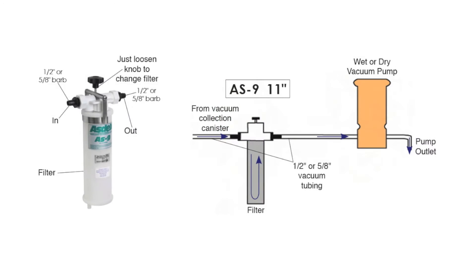The unit operates under vacuum and is to be installed in-line on the central vacuum line. The manifold has pipe thread fittings but may also be connected via flexible vacuum line if fitted with the provided barb connectors.